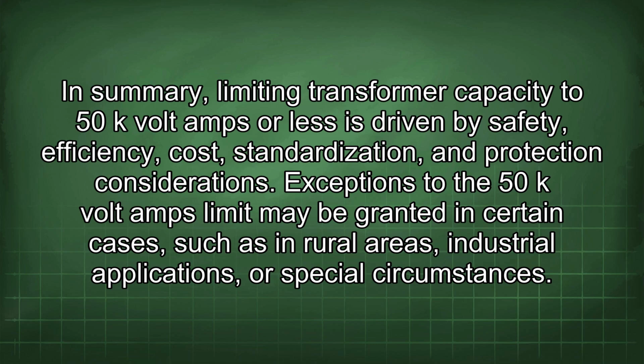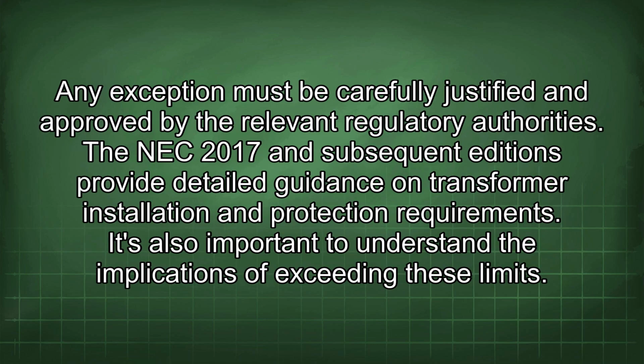Exceptions to the 50 kVA limit may be granted in certain cases, such as in rural areas, industrial applications, or special circumstances. Any exception must be carefully justified and approved by the relevant regulatory authorities. The NEC 2017 and subsequent editions provide detailed guidance on transformer installation and protection requirements. It's also important to understand the implications of exceeding these limits.